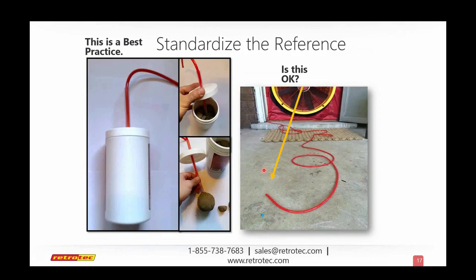Okay. Wait, wait 1 second. I want to clarify. Sorry. Is that the only time that it shows up is when you are telling the gauge to perform a test, either with at pressure or at speed. So you actually can perform a test using the speed control on your fan. But if you want to use the at feature, then I actually have to engage it either doing the test or thinking that it's doing the test. So I can actually use my duct tester or blower door with the speed control on the side of the fan. And the only way that I can do that is if the speed control is disconnected.